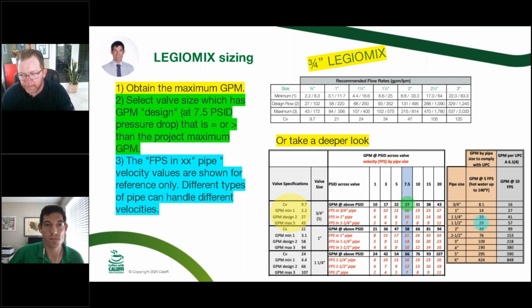Yeah, I think the big takeaway from the slide that we've put together here is right off the bat on the far right-hand side where you see it, the 10 feet per second. My personal take is just pretend that doesn't exist. Don't use that. You're begging for trouble on that. You have to be conscious of that 5 feet per second. That really is the magic number you want to pay attention to. But again, it comes down to what material are you using. Max might be using copper. I might be using Nupi PP-R. It's going to come into play on it.